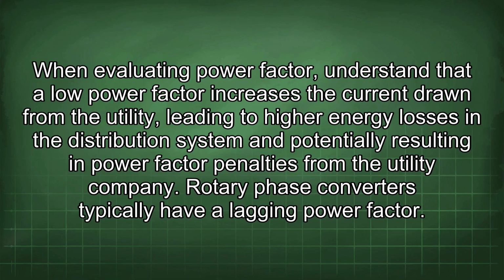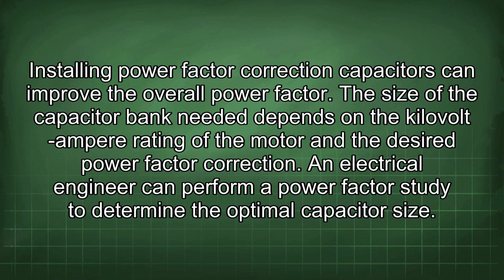When evaluating power factor, understand that a low power factor increases the current drawn from the utility, leading to higher energy losses in the distribution system and potentially resulting in power factor penalties from the utility company. Rotary phase converters typically have a lagging power factor. Installing power factor correction capacitors can improve the overall power factor. The size of the capacitor bank needed depends on the kilovolt-ampere rating of the motor and the desired power factor correction. An electrical engineer can perform a power factor study to determine the optimal capacitor size.